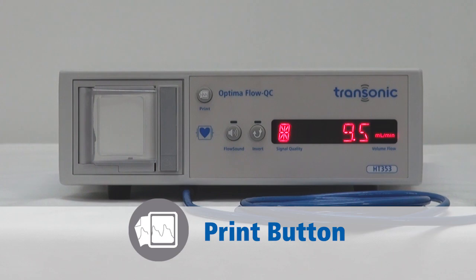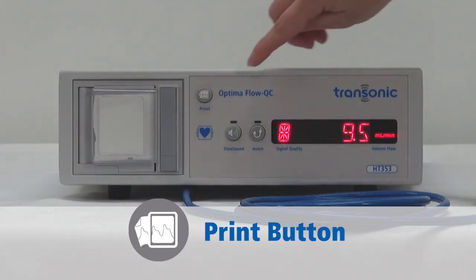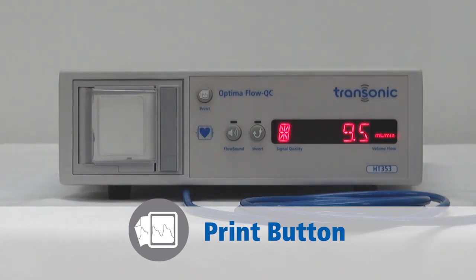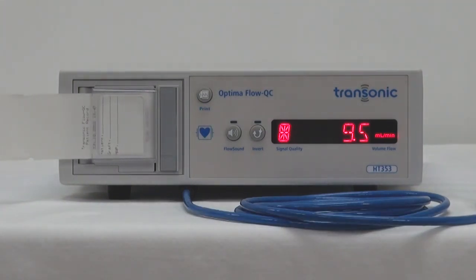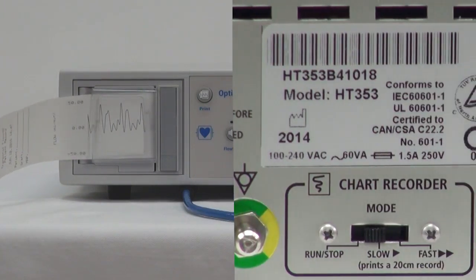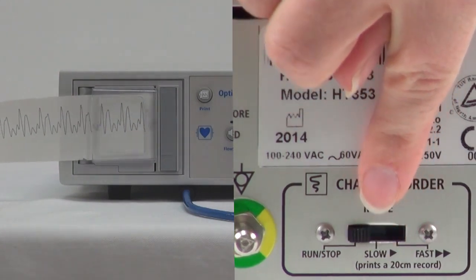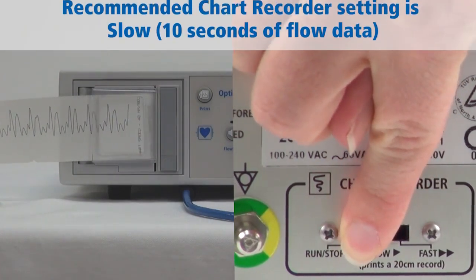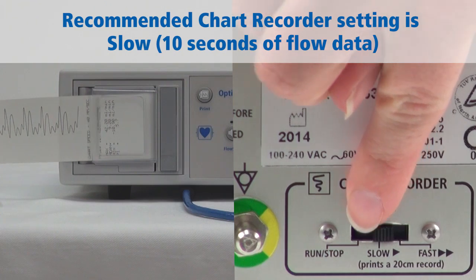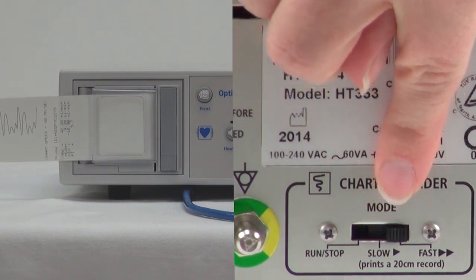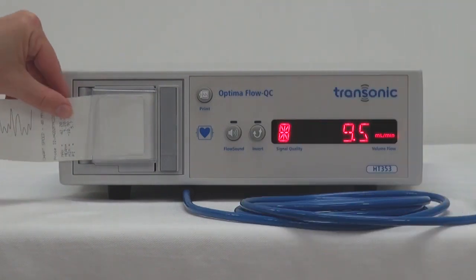Press the print button to start the chart recorder to get a physical printout of the flow waveform. You can set the rate of printing through the chart recorder switch. Run stop will print continuously until manually stopped. Slow prints 10 seconds of flow data. Fast prints 5 seconds of flow data.